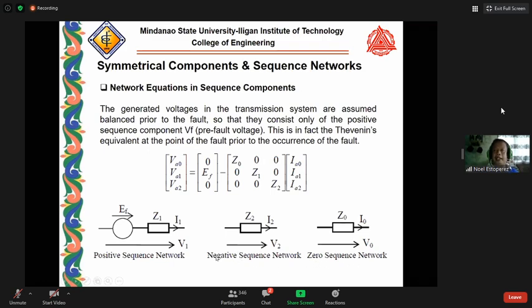So given the positive sequence network, negative sequence network, and zero sequence network, if we want to know the case for the three asymmetrical faults, the single line to ground, double line to ground, and line to line, we just combine and reconfigure these, as we'll see in the following slide. For a single line to ground fault, the positive sequence network will be connected in series with the other networks, so positive sequence network in series with negative, in series with zero sequence network.